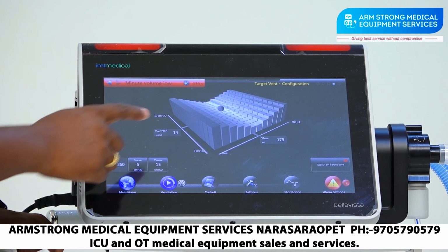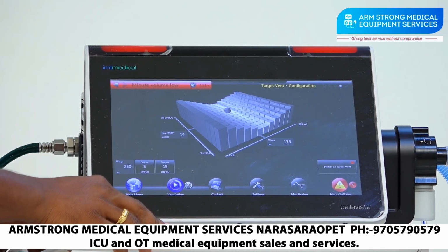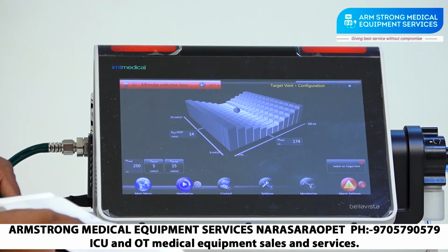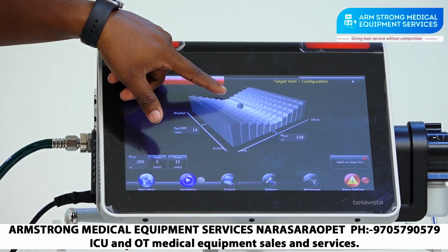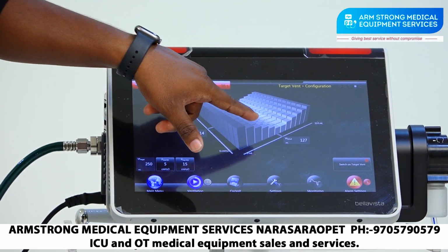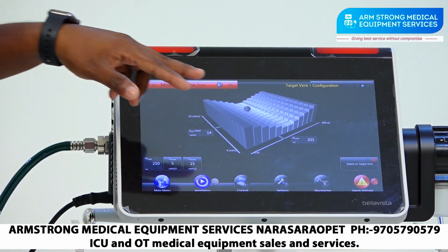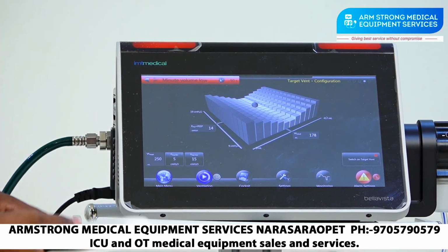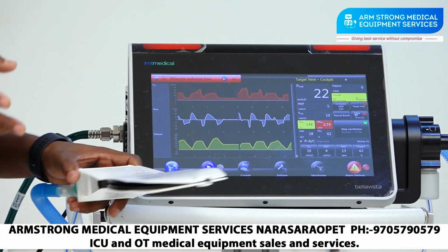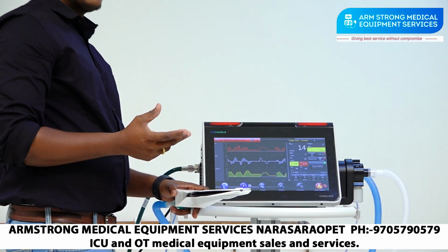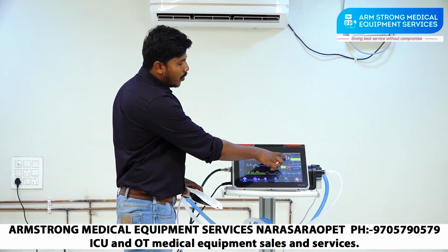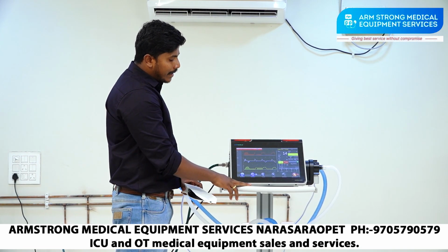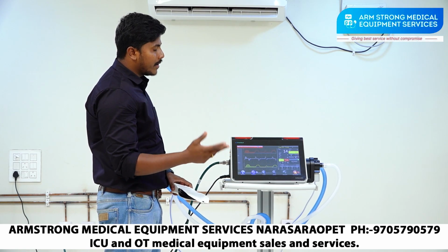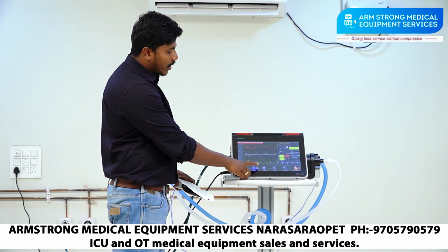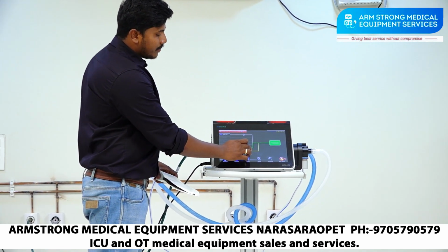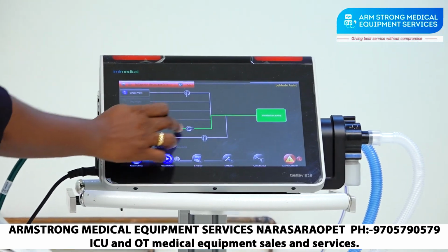In this target vent configuration, especially we have this tracking ball. This is very useful. How target vent is working we can see with this track ball. See, the track ball is moving, showing how much actual VT there is and, when the patient peak pressure goes high, how the track ball moves at that time. In target vent, for particular kinds of patients, such as some lung, heart or trauma cases, the peak pressures will go very high but the tidal volume won't be achieved. For those patients we will select this target vent, which in other companies' terminology is a volume guarantee. On this ventilator we have target vent. They named it differently but all are the same. Now I switch off this target vent.